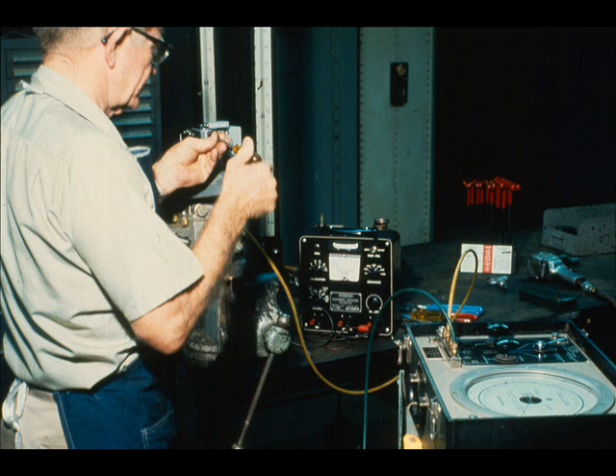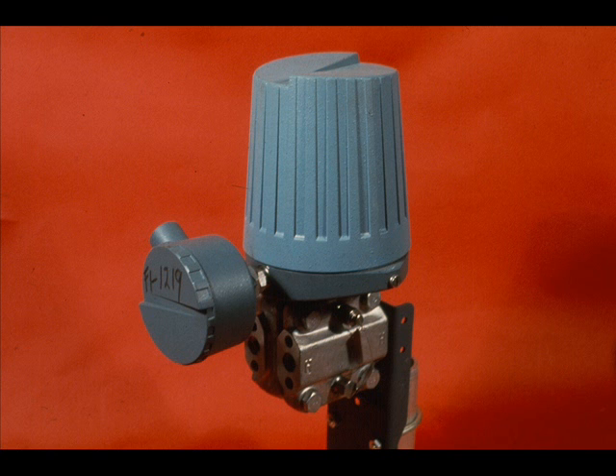Our first calibrations will be done in the shop. We will assume we have a work request to change the range of this Foxboro E13DM differential pressure transmitter from 0 to 50 inches to 0 to 150 inches of water. The output range is 10 to 50 milliamps.